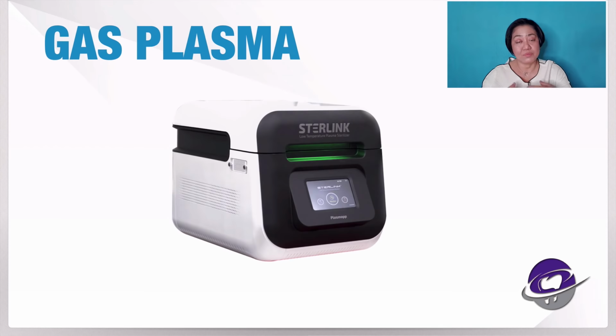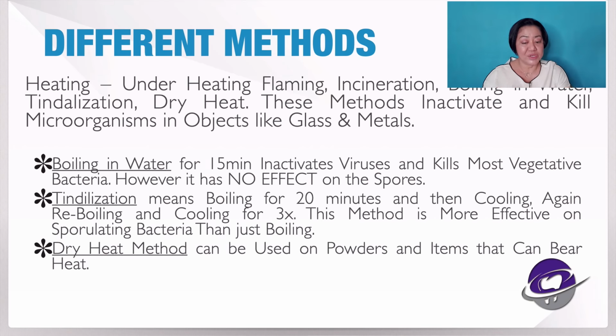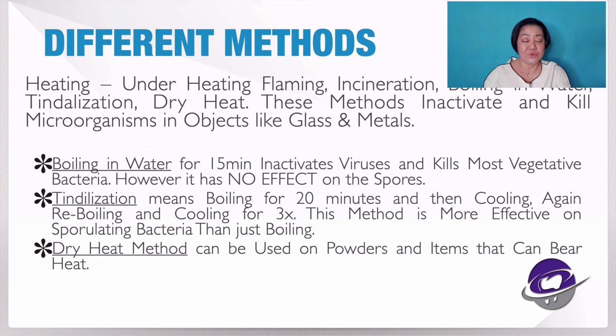Now, of course, if you like to boil things to make it even cheaper, fine. But I will recommend tyndallization, meaning boiling for 20 minutes, cooling it, and then reboiling, and then cooling it again, 3 times. If that is what you really need to do because you don't have an autoclave, this is the cheapest way of sterilizing. So not just boiling it once, but you boil it 3 times every 20 minutes. And then, of course, the use of the dry heat method. But again, all these methods, nothing can compare when it comes to the steam or autoclave.